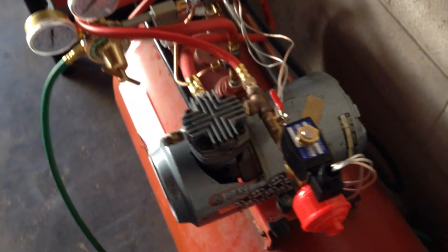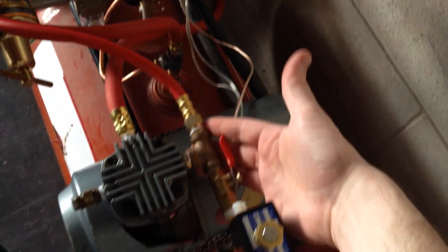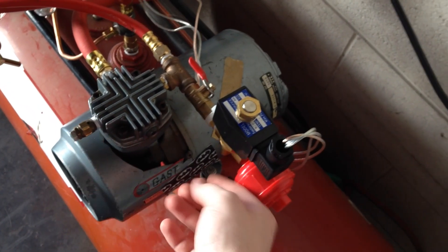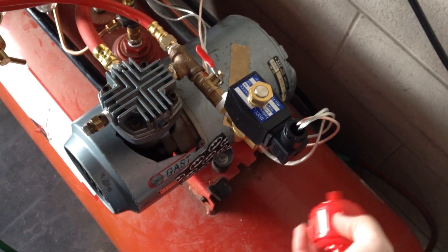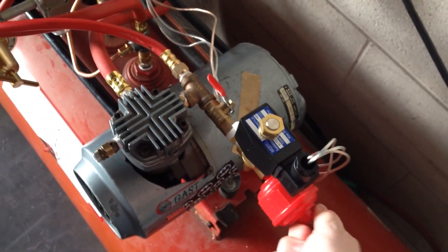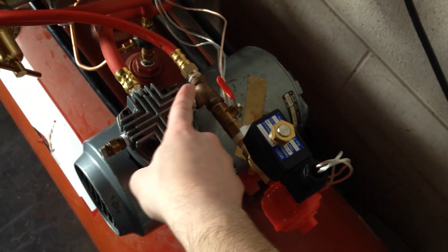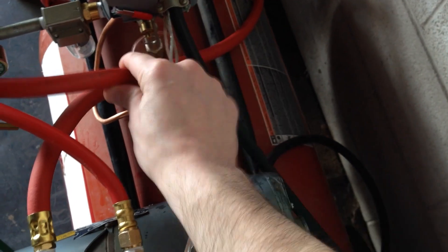I have a solenoid valve. This is the oxygen inlet right here. Basically when the pump is not on, the extra air can come out of here. I have this on here just to quiet it down — it's not really filtering anything. But when the pump does turn on, this valve closes and all the oxygen just goes into the pump and then out down into here.